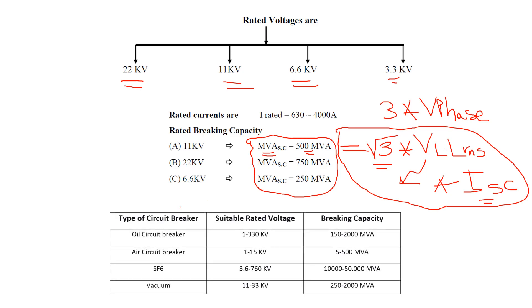The circuit breakers used in medium voltage include oil circuit breakers, air circuit breakers, SF6 circuit breakers, and vacuum circuit breakers. Oil circuit breakers operate from 1 kV up to 330 kV, covering both medium and high voltage levels, with breaking capacities from 150 MVA up to 2000 MVA.